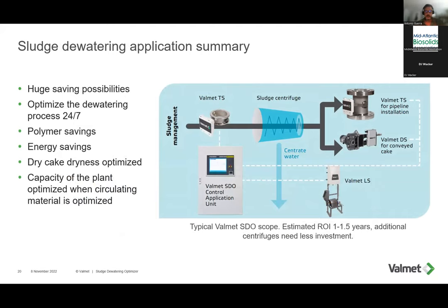So in summary, these instruments and control packages do present new savings possibilities by not only trying, but actually optimizing the dewatering process based on how it changes on a 24/7 period by saving in polymer use, saving in energy use, optimizing your dry cake dryness, and also trying to minimize the amount of centrate solids that need to be reprocessed and circulated back upstream.